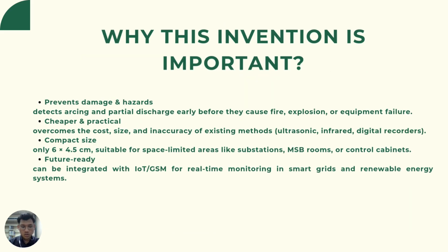Why is this invention important? It can prevent damage and hazard, such as detecting arcing and partial discharge early before they can cause fire, explosion, or equipment failure. Secondly, it is cheaper and practical. It overcomes the cost, size, and accuracy issues of existing methods like ultrasonic, infrared, or digital recorders. Because of its compact size, only 6 times 4.5 cm, it gives you a cheaper price, and it is suitable for space-limited areas like substation, MSB room, or control cabinets. For the future, it can be integrated with IoT or GSM for real-time monitoring in smart grid and renewable energy systems because of the compact size.